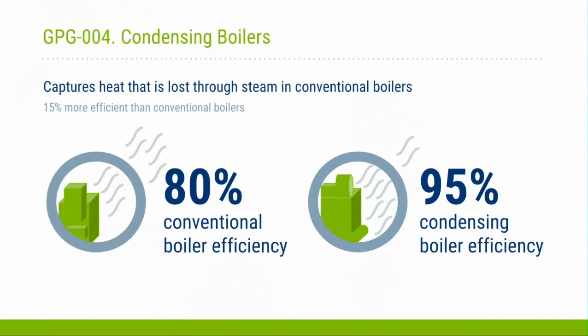At the highest level, condensing boilers are shooting to improve boiler efficiency, and they do that through capturing the heat that is lost through steam, basically water vapor, in the flue gases, and they condense that back down out of the flue gases and put that heat back into the system, increasing the total efficiency of natural gas usage to heat delivered. They're about 15% more efficient than conventional boilers at rated conditions, and can be even more efficient in real-world applications. Next slide.